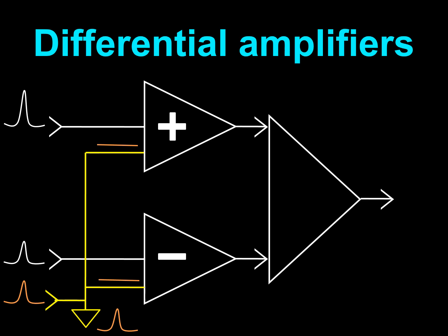The wave represented in cream color arriving from the brain to the input of the lower pins of each single-ended amplifier and connected to the ground will be, by virtue of this connection, viewed by the bulk of the amplifier as having no voltage. Thus, the amplifier will consider it for further manipulation as zero voltage or neutral. This will be so regardless of the original amplitude of the wave arriving at the mentioned point.